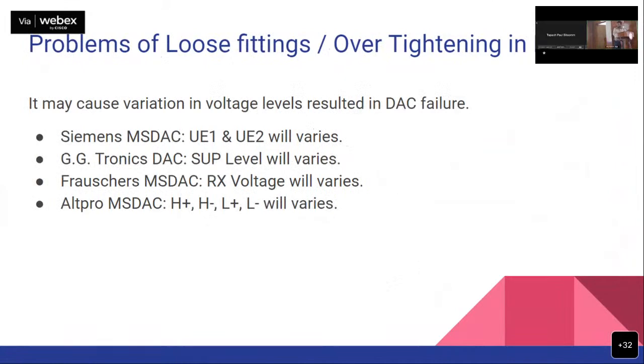Again, sir, because of lesser tightening or more tightening of this torque, we are facing some problems. The first failure I discussed, sir, was when the first track went down due to the sensor falling on the rail, and the next track went down due to this same issue. This was the GG-tronic, sir, so SUP level variation occurred because of some loose fitting. These type of failures we are facing, sir. In Siemens, the UE1, UE2 voltage will vary, and we have to recalibrate the system. We can recalibrate the system from the hut only, and once recalibrated it will settle to its 3 volt level. Then in Altpro, these levels will vary and the system will go to a failed state, and again it will recover using some supervisory reset, or because some of the redundant system is working.